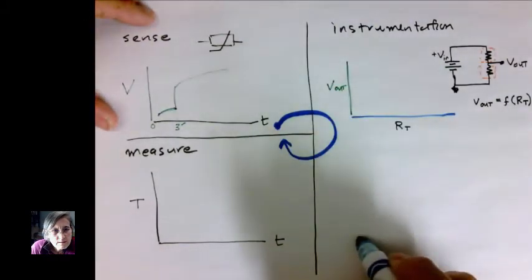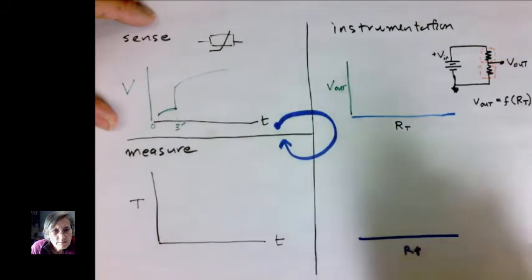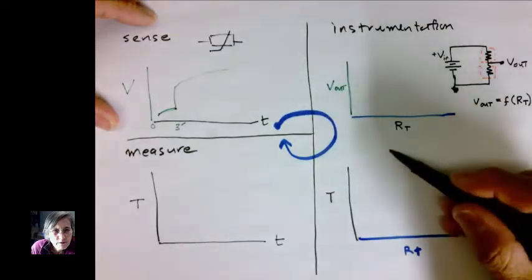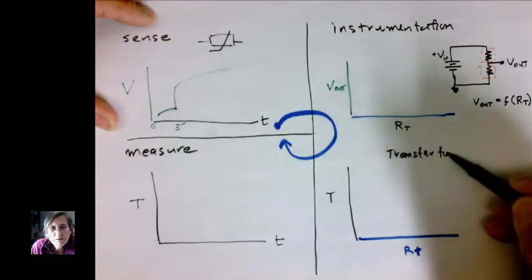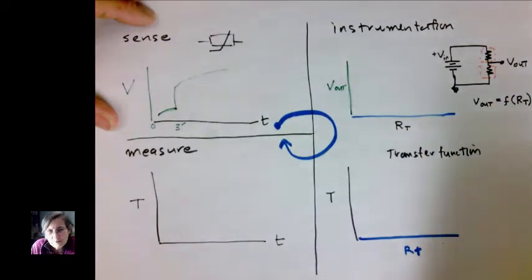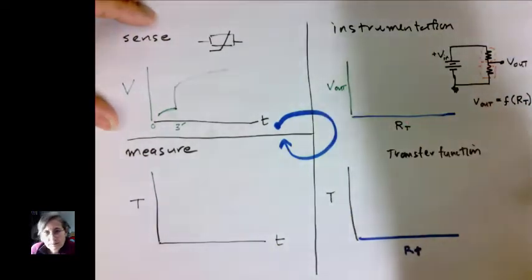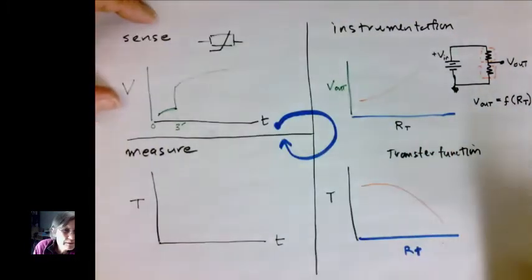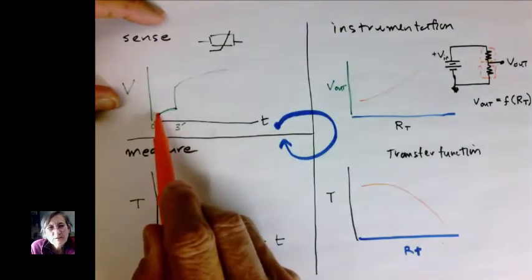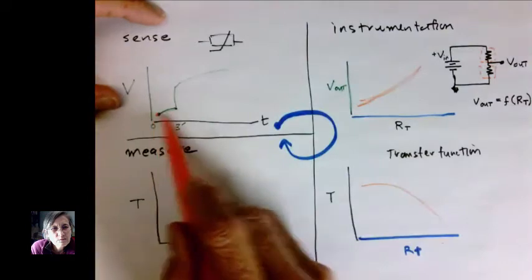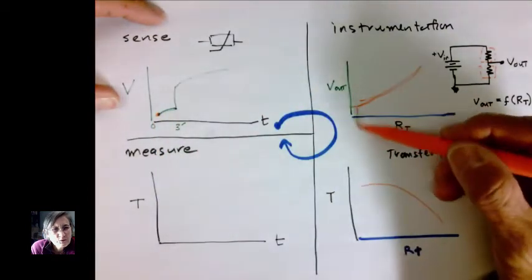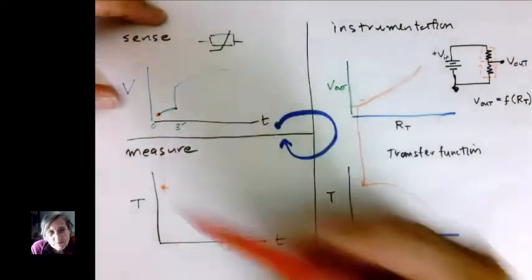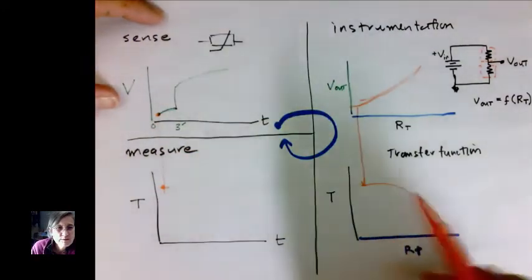Now to get to our desired quantity we need to convert that V out value to a temperature value and we do that by using the transfer function of the thermistor and that is provided in the documentation. I'm just going to add some curves here, these may or may not be right but I'm just trying to illustrate that we take the data point in one domain in the voltage time domain and we convert it through the voltage resistance domain and then the temperature resistance domain to get to the temperature time domain.